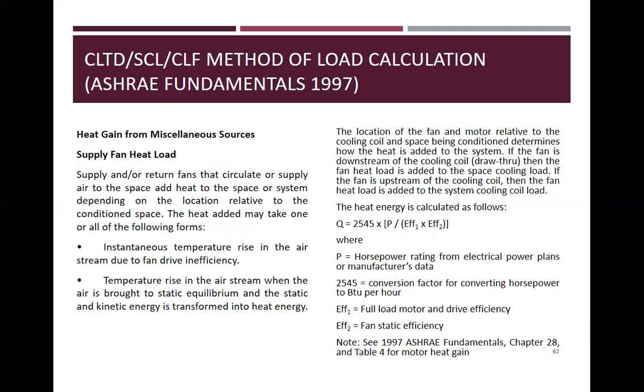The location of the fan and motor relative to the cooling coil and space being conditioned determines how heat is added to the system. If the fan is downstream of the cooling coil, draw-thru, then the fan heat is added to the space cooling load. If the fan is upstream of the cooling coil, then the fan heat load is added to the system cooling load. That's it. Because after the coil, in draw-through, it is after the coil. For upstream of the coil, it is before, so you put it in your system load.